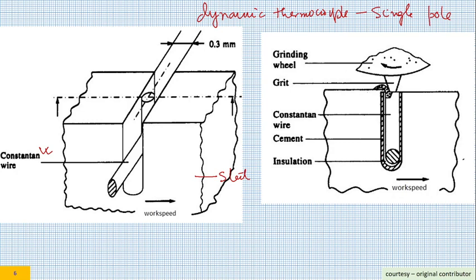Cement is nothing but resin. We use the resin so that there is insulation between the constantan and the steel, so there is no short circuit. Only during measurement, during chip formation, the constantan would also form a chip, and here a hot junction would occur. This is very near the grinding zone or on the grinding zone, so that grinding zone temperature can be measured.